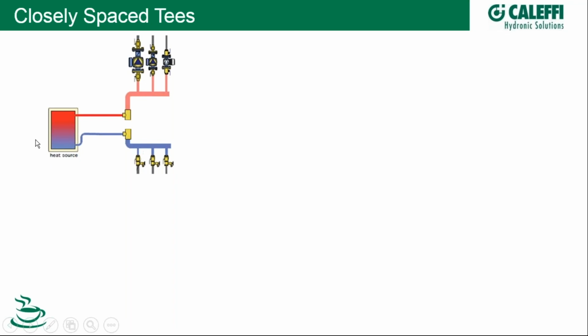Another example is some manufacturers are saying that if appropriately designed, the secondary system on a condensing boiler can accept full flow, meaning it can accept 100% of the design flow created by your pumps up here, meaning it also can accommodate full flow through the condensing boiler. Now, I don't know the models offhand, but I do hear that from time to time on some models of some manufacturers.